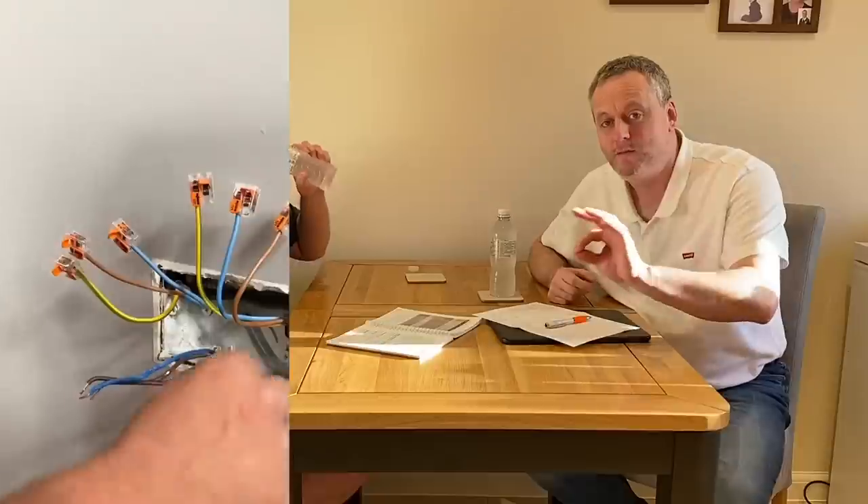Just one point about disconnecting conductors — we've had this in another video where you remove the CPC sleeve and find conductors twisted together. Not in the 80s anymore. I think I was taught to put two CPCs in one piece of sleeve — it's common, isn't it. The thinking was that if one becomes disconnected the circuit stays continuous. I wouldn't do it now. When you're trying to isolate circuits off, having twisted conductors is an absolute disaster — especially with an RCD trip where we know we have a fault and we need to completely remove those conductors.